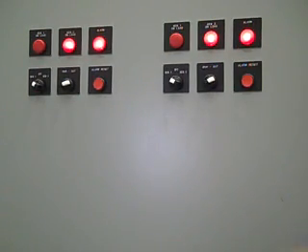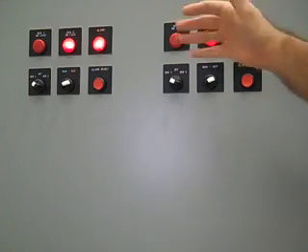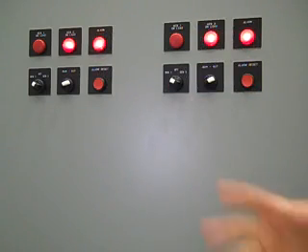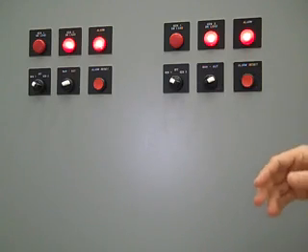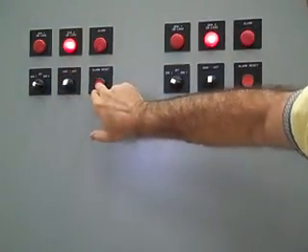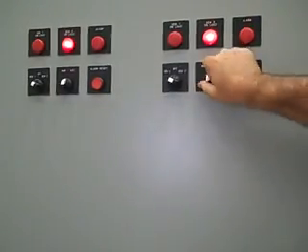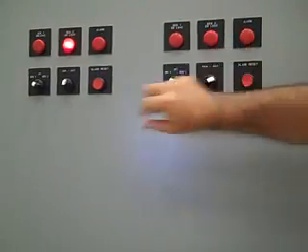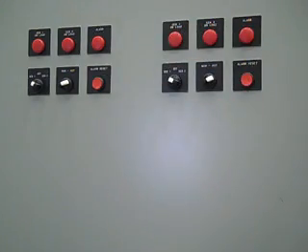I can reset, let's say this had happened. You can go to Gen 1 in the field, reset the generator, and clear whatever the fault was, maybe it ran out of fuel. God knows what happened there, but you went ahead and reset it, and now the unit is ready to run again. What you can do is put the switch in manual and reset the alarm. Okay, the alarm is reset, and I'm going to simulate here that the voltage on Gen 1 is good again, and I flip back to auto. The unit is going to go back to generator 1.